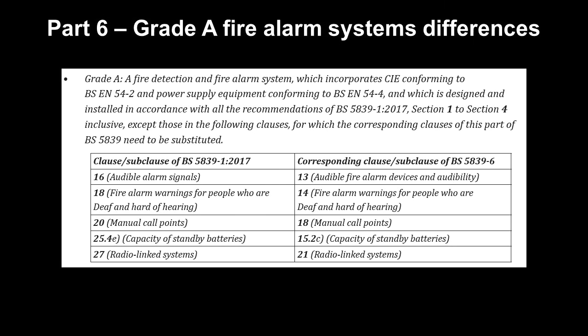And I hope that makes sense. A good example is manual call points. So it's not required to install manual call points in the same way as it is on part 1 in a domestic premises. It's a recommendation in certain areas. Just an example, the capacity of the standby batteries. You'll be surprised actually, in a domestic premises you have to install quite big batteries and battery backup. So be careful on that. Don't just install a twin flex system and think whatever batteries come with it are absolutely fine. You need to do battery calculations, and you don't use clause 25.4e on part 1. Use 15.2c on part 6. I hope that makes sense.